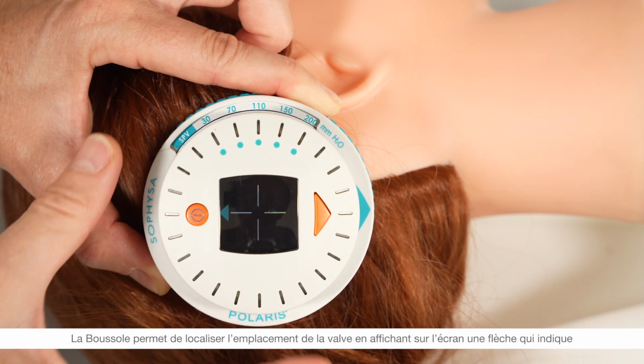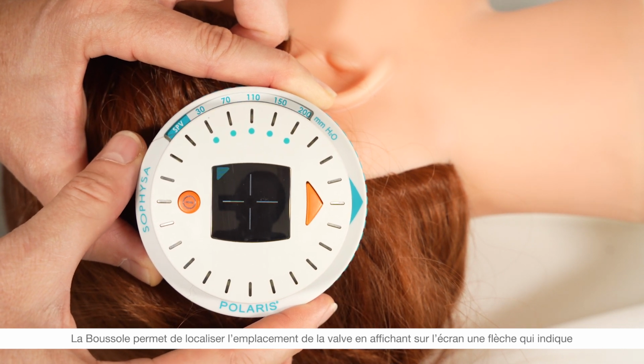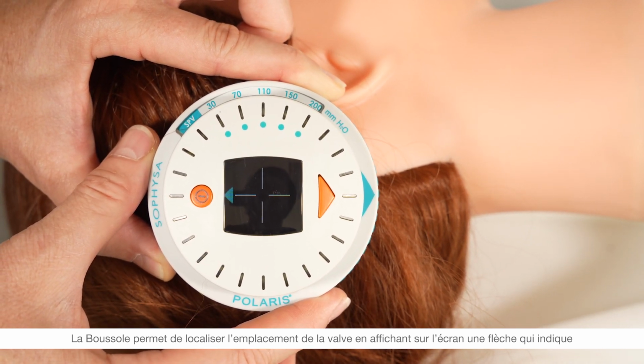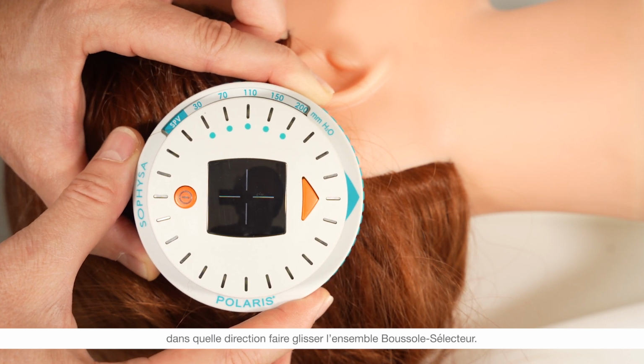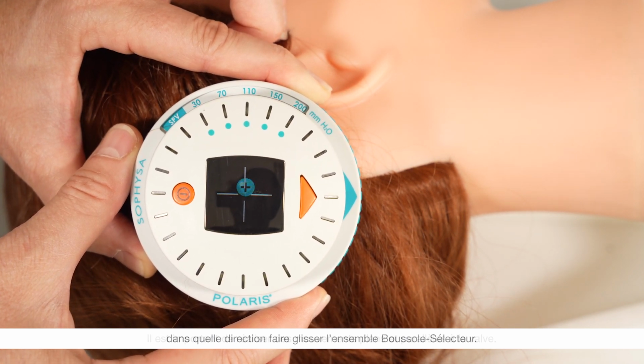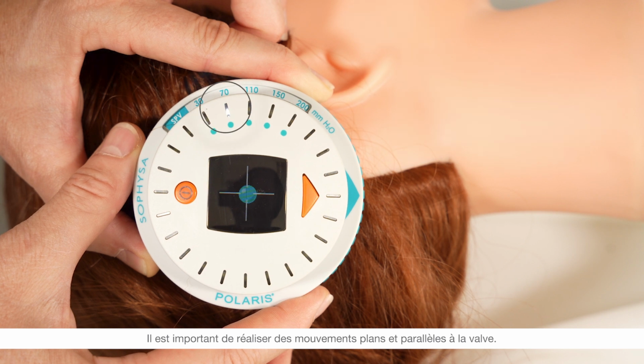The compass inside the locator will now automatically localize the valve. Instructions will be displayed on the compass screen, indicating the movement of the locator so that it will be positioned above the center of the valve's rotor. When the center is close, a dot will appear on the screen. Move the locator until this dot is centered in the middle of the target. Now, the instruments are centered properly above the implanted valve. Here, it is 70 mm of water.